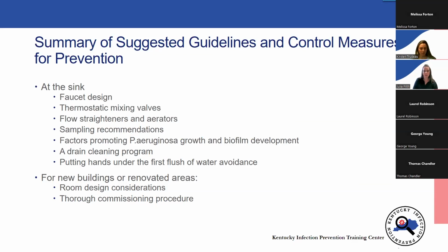They also had guidance for new buildings or renovated areas and considerations around room design—one being to only put sinks where you need them. You want sinks available for people to clean their hands appropriately, or for other water needs, but not to add extra water sources unnecessarily. Choose a sink design with the splash directed away from the drain, and if splashing is unavoidable, make sure the patient's bed and other medical equipment are outside the splash area. Prior to opening a renovated or new building location, make sure a thorough commissioning procedure is done within that facility.